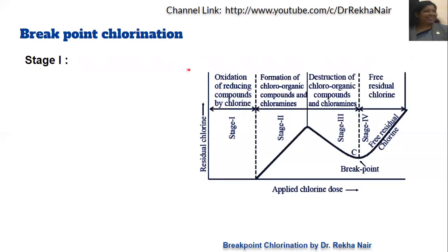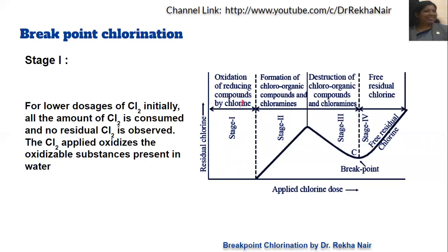In Stage 1, which is the oxidation of reducing compounds by chlorine, as we increase the applied chlorine dose along the x-axis, the chlorine sent into the water is completely utilized. Residual chlorine remains at zero — the chlorine applied is consumed entirely in oxidizing the reducing compounds present in the water.